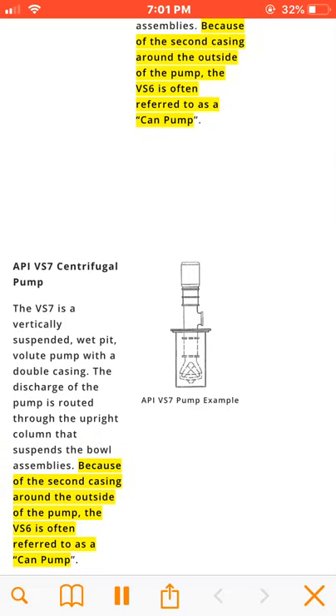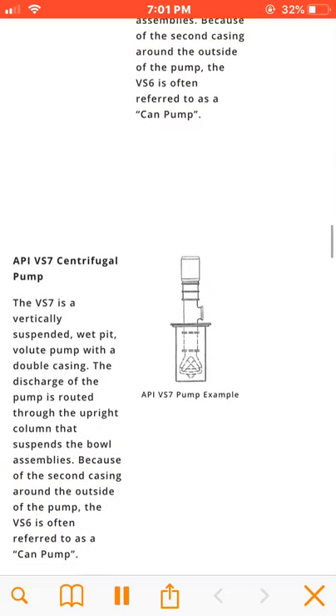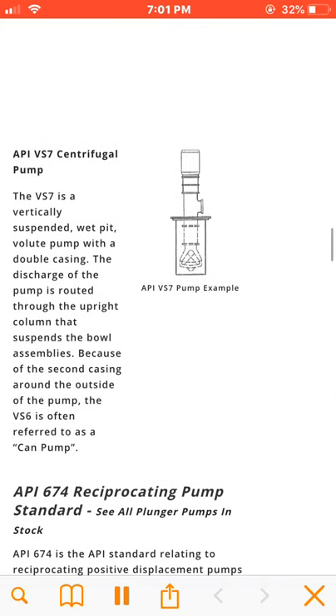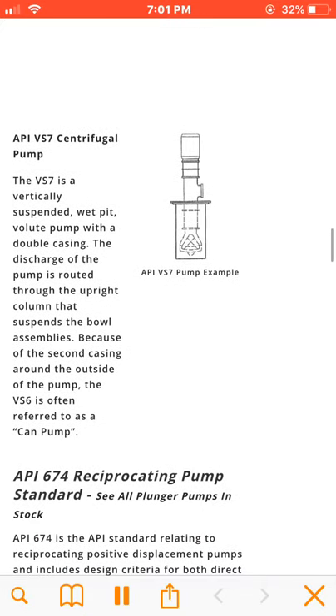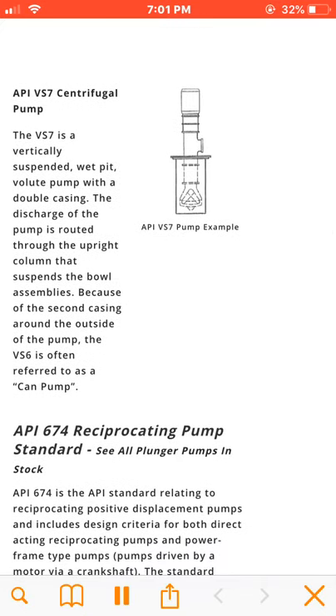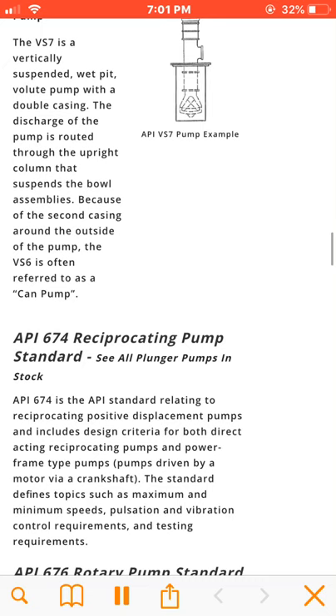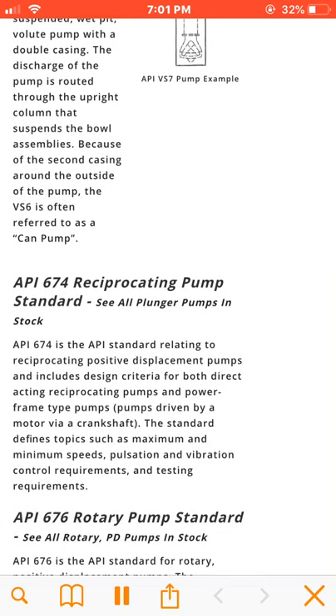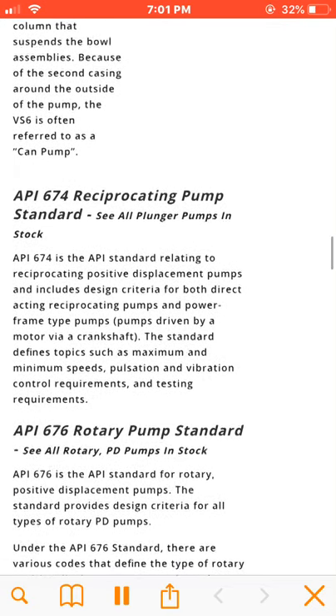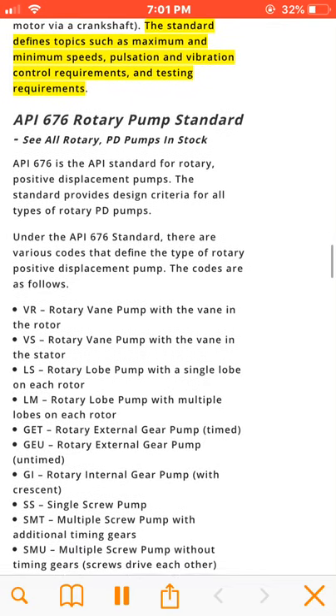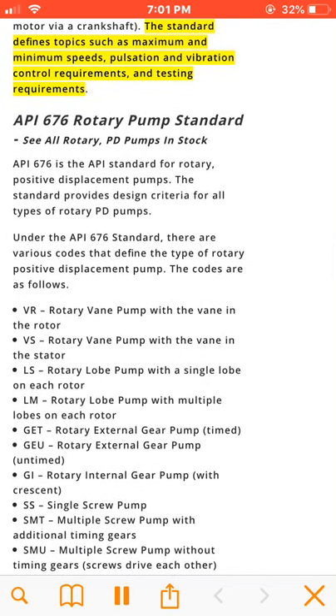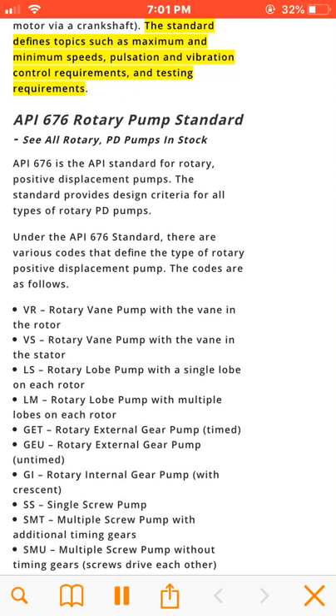API 674 is the API standard relating to reciprocating positive displacement pumps and includes design criteria for both direct-acting reciprocating pumps and power frame type pumps — pumps driven by a motor via a crankshaft. The standard defines topics such as maximum and minimum speeds, pulsation and vibration control requirements, and testing requirements.